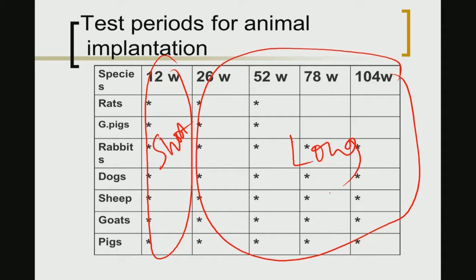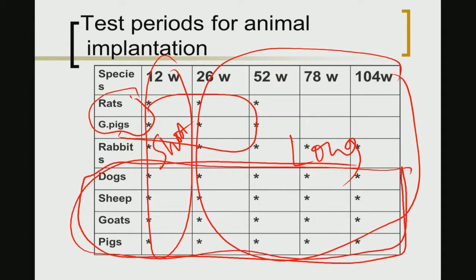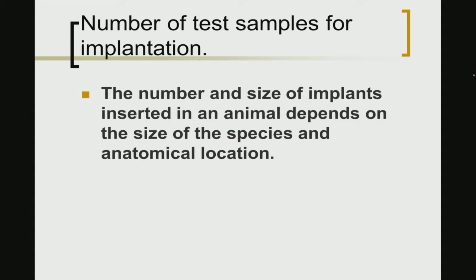In the table, rats and guinea pigs are short-term cases — extending perhaps up to 52 weeks — but rats and mice often cannot survive such longer time periods once implantation experiments begin. The four animals listed in the later half of the table — dogs, sheep, goats, and pigs — are used for long-term implantation studies.